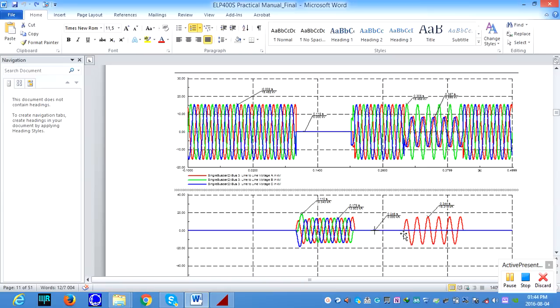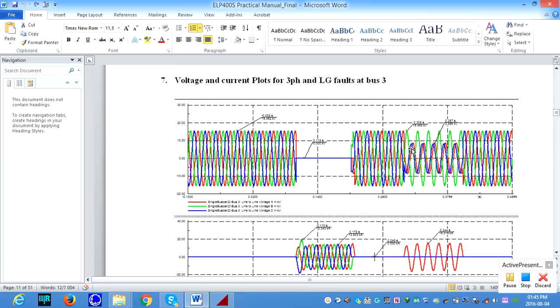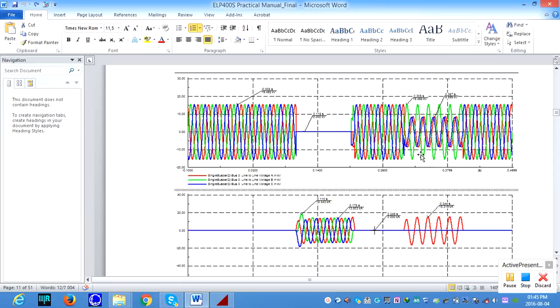It means the fault current goes to 0 and the system is trying to build up the voltage. Okay. When the system is building up the voltage up to 0.2, there is no fault. The system has fully recovered the voltage. And at 0.2 seconds, we introduce a line to ground fault on phase A. So that's why the phase A voltage goes down, but the other two phases remain the same, and the phase A current will build up. And after 0.3 seconds, okay, I think after 0.4 seconds, the fault is cleared and the system tries to build up. The total simulation time here they used is 0.5 seconds.